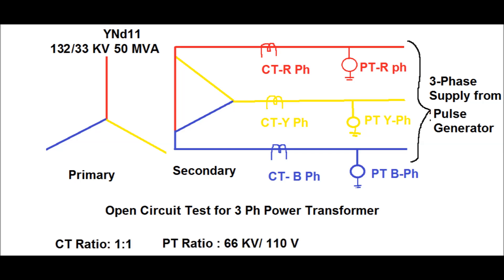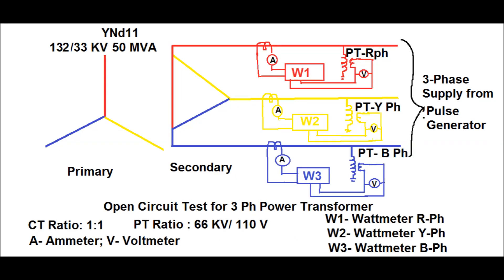In the arrangement shown in this diagram, the PT ratio is 66 kV to 110 V, that is a ratio of 600. The CT ratio is 1:1 since the CT current will be very small, which is why the CT ratio is used as 1:1. The three-phase supply given from the pulse generator is of the order of 33 kV.